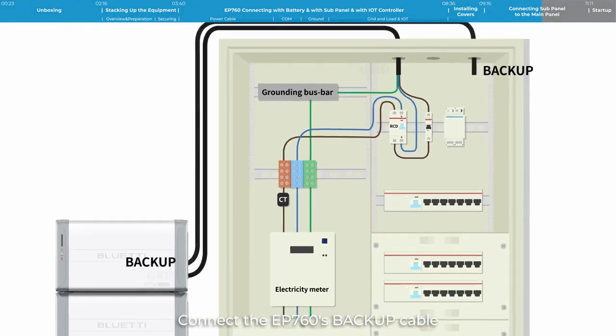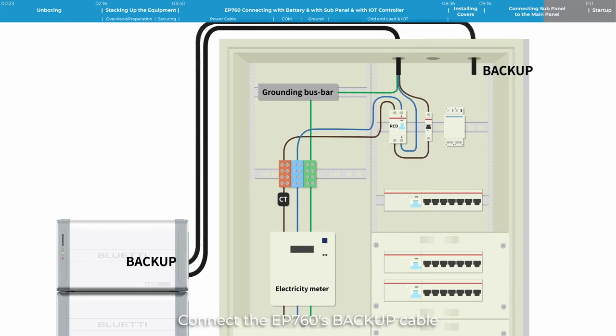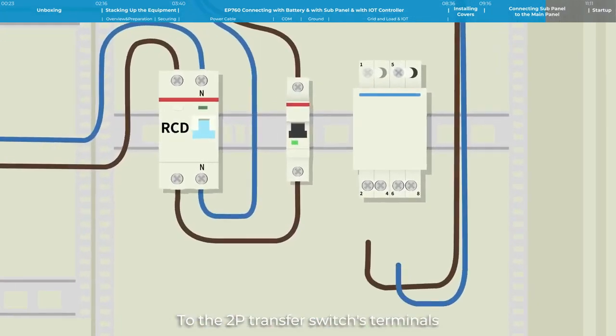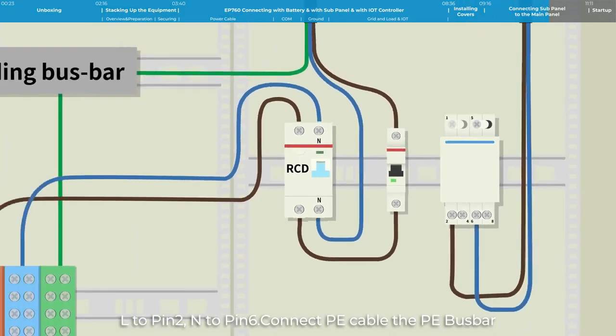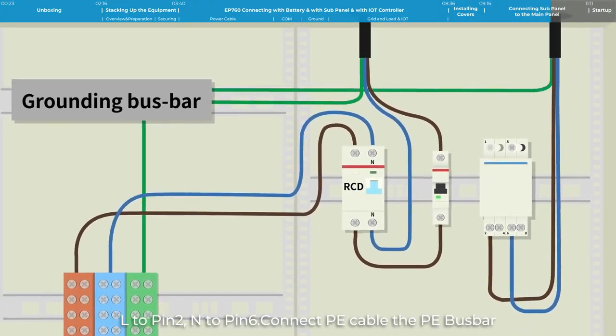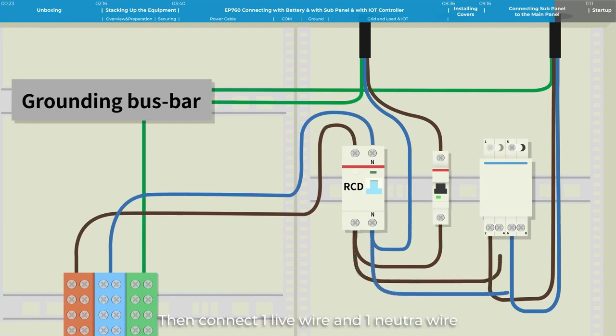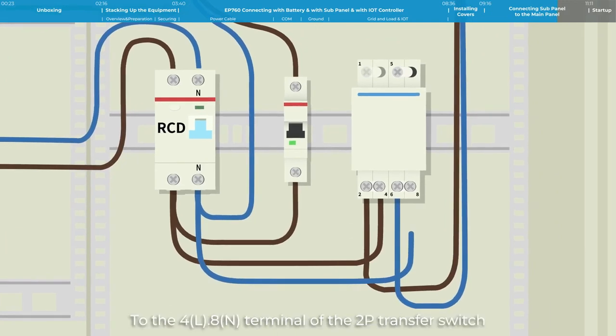Connect the EP760's backup cable to the 2P transfer switch's terminals. L to pin 2, N to pin 6. Connect PE cable to the PE bus bar. Then, connect one live wire and one neutral wire from the 2P RCD terminal to the 4, 8 terminal of the 2P transfer switch. L to pin 4, N to pin 8.